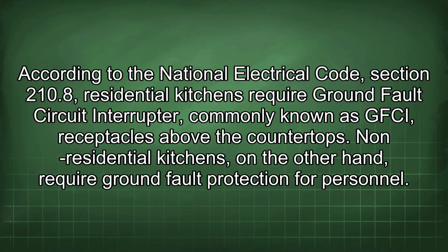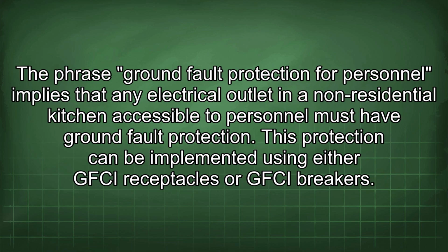According to the National Electrical Code, Section 210.8, residential kitchens require ground fault circuit interrupter, commonly known as GFCI, receptacles above the countertops. Non-residential kitchens, on the other hand, require ground fault protection for personnel. The phrase ground fault protection for personnel implies that any electrical outlet in a non-residential kitchen accessible to personnel must have ground fault protection. This protection can be implemented using either GFCI receptacles or GFCI breakers.